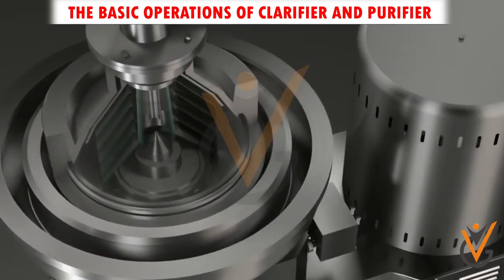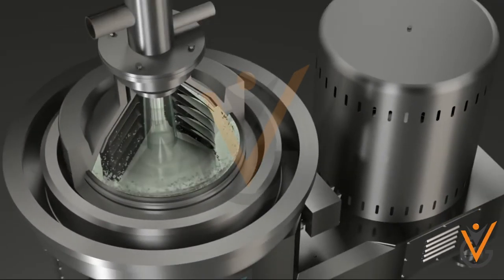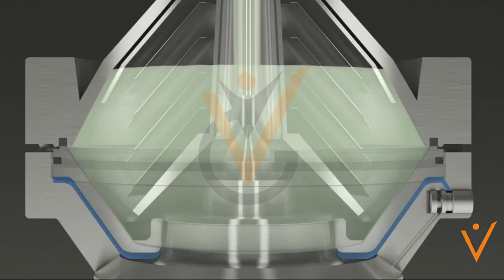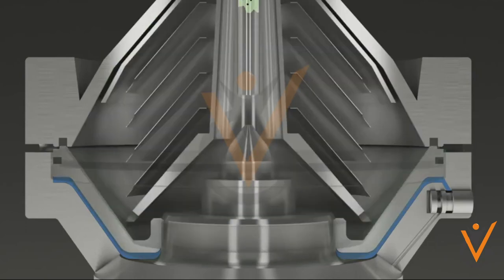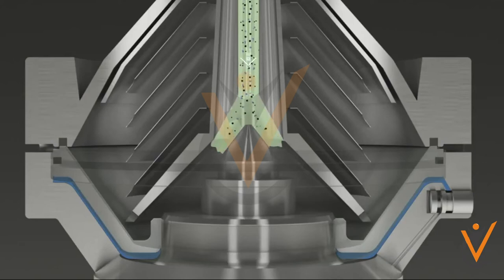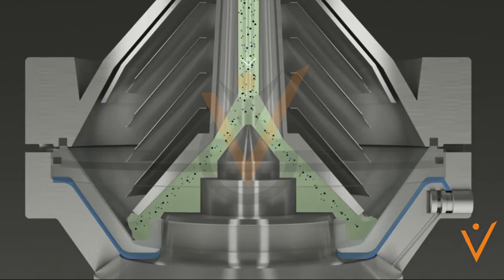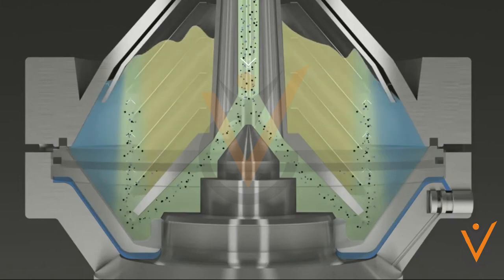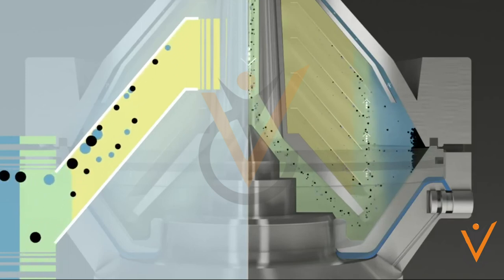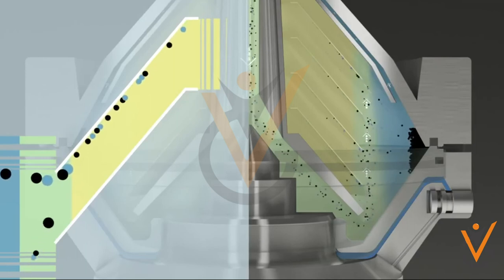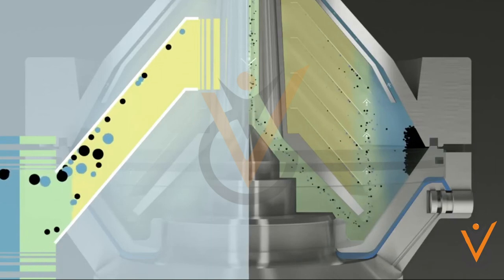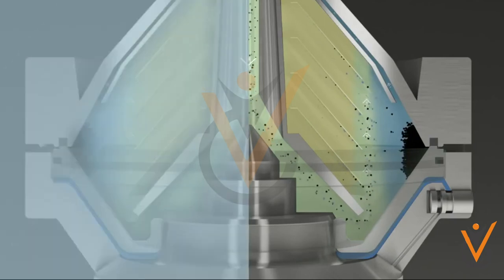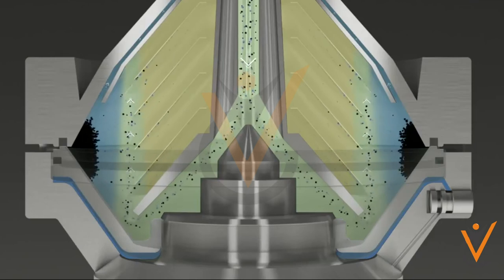The basic operations of clarifier and purifier: It contains a stack of disc numbering up to 150 and is separated from each other by a very small gap. A series of holes are aligned in each disc near the outside edge which permits the entry of dirty oil. Due to the difference in gravity and centrifugal force, the heavier impure liquid, water, and particles move outside and lighter clean oil flows inwards and gets separated. The collected sludge and impurity can be discharged continuously or at a time interval, depending upon the construction, automation, and system incorporated.